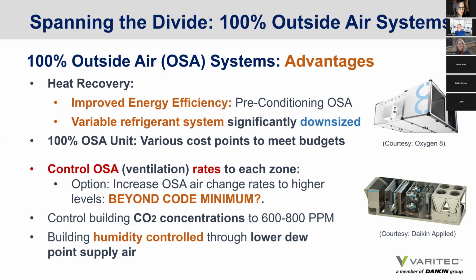In an all mixed air system, are we sure we're getting the outside air distributed to all the zones in an all air system? Well, we presume so, that actual adequate mixing occurs at the air handling to distribute percentages uniformly throughout a building. But if you decouple the outside air, you can be assured you're bringing the outside air necessary to each zone. And then you have the opportunity to say whether or not you want to optimize indoor air quality by increasing the outside air flow rate beyond code minimum.